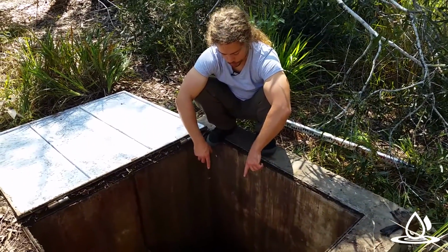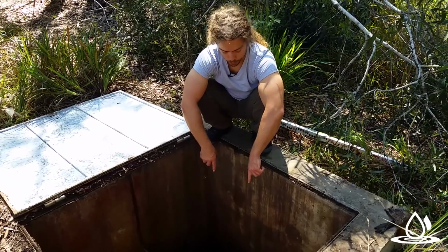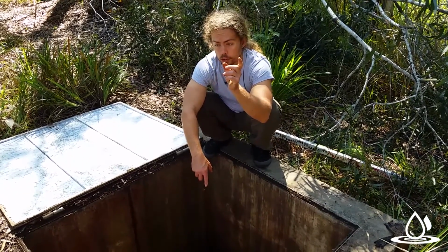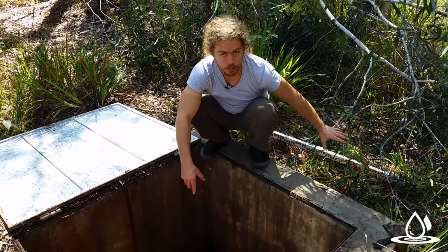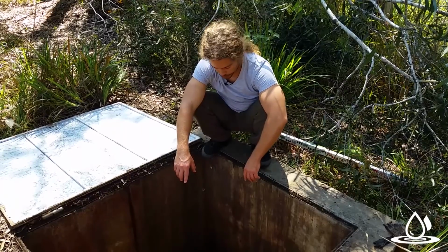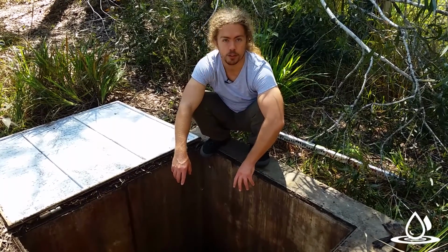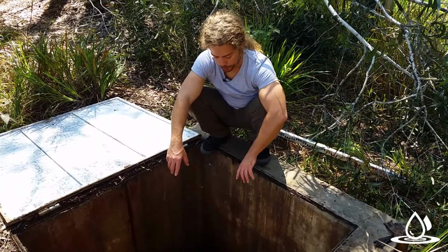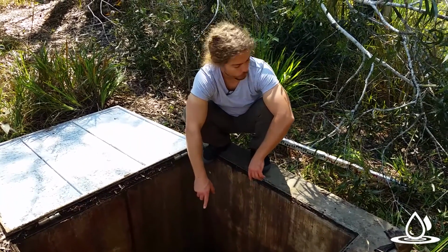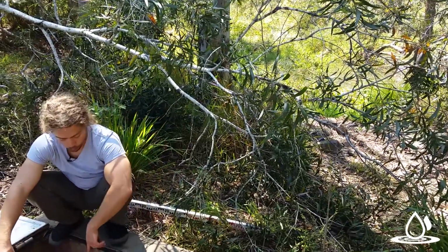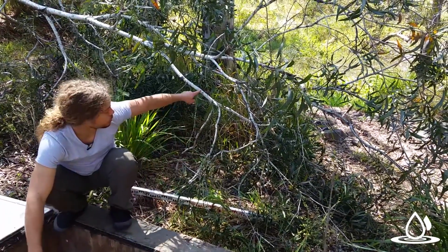Then the question becomes, why is the water backwatering on this side? There could be two reasons for that. The first one could be that there could be a blockage in this pipe somewhere, or a partial blockage. That's possible. It's like a 300 mil diameter pipe though. It's a fairly serious pipe. That seems unlikely for there to be a blockage here, particularly with the riser plate in the way, unless there's a blockage right at the downstream end. Or more likely than that, it's literally just the water.